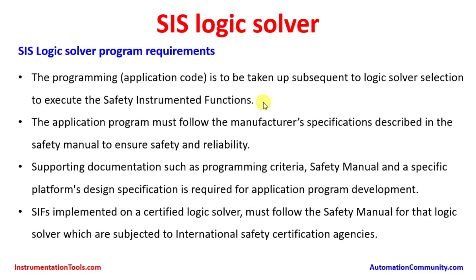SIS logic solver program requirements — we will go over a few key points. The programming application code is to be developed subsequent to logic solver selection in order to execute the safety instrumented functions. The type of programming language has to be finalized once the type of logic solver for the safety instrumented system is selected. The application program must follow the manufacturer's specification prescribed in the safety manual to ensure safety and reliability.